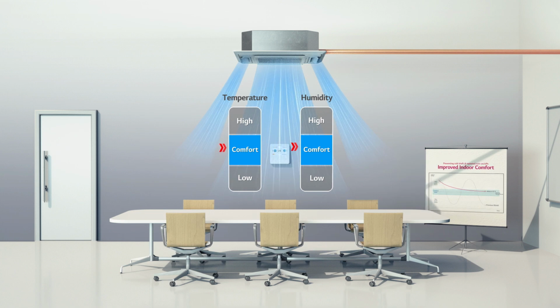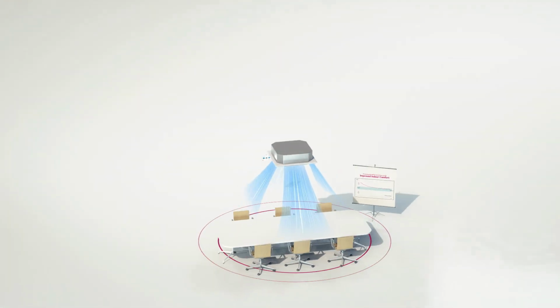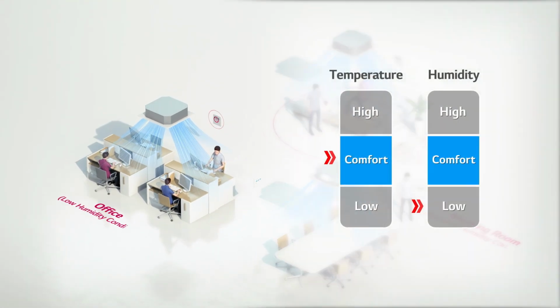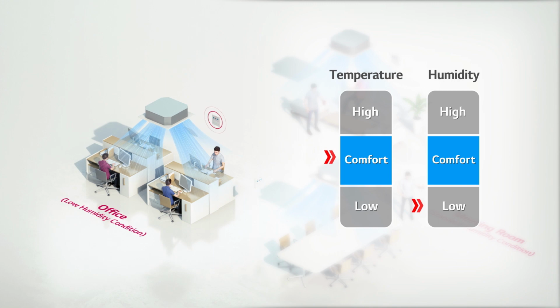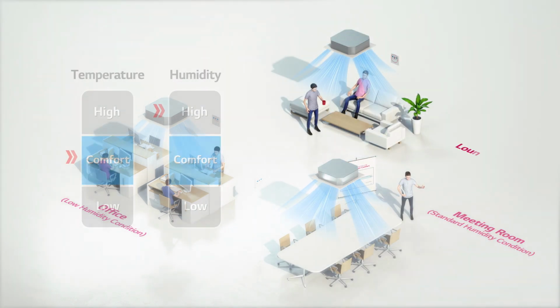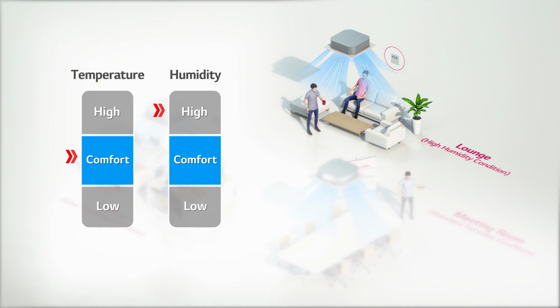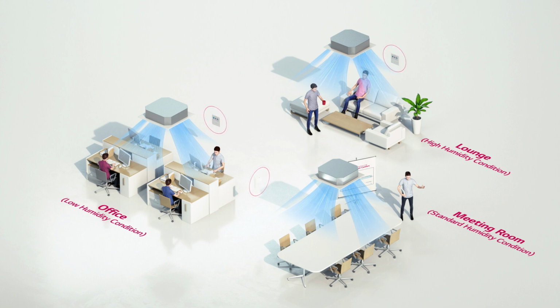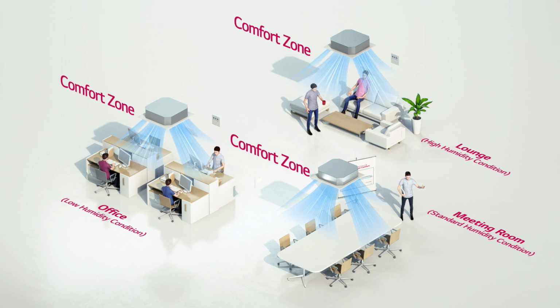Now, there are some places in a building that require different air conditions due to its purposes. Take office, for instance, wherein a lot of electronic devices are put together. It's a place with low humidity, thus mild air is discharged in order to increase humidity level. On the other hand, for relatively humid places such as lounge, where people come to have a coffee break, colder air discharge is necessary to lower the humidity level. Thanks to the humidity sensing technology, dual sensing control manages to keep every place comfortable even when indoor environment and air conditions are all different.